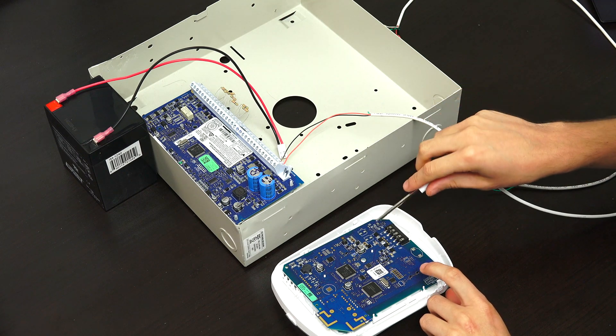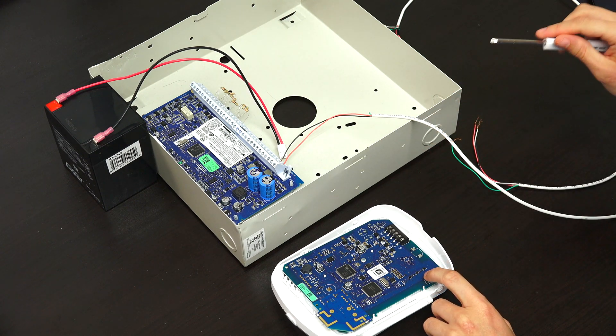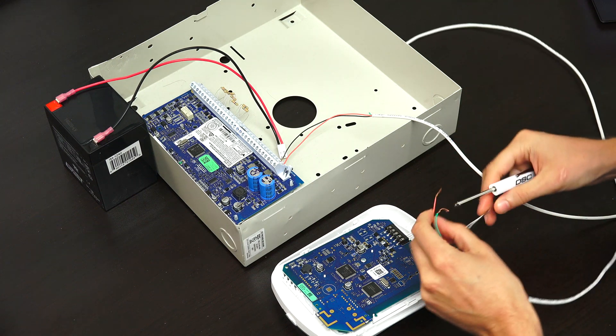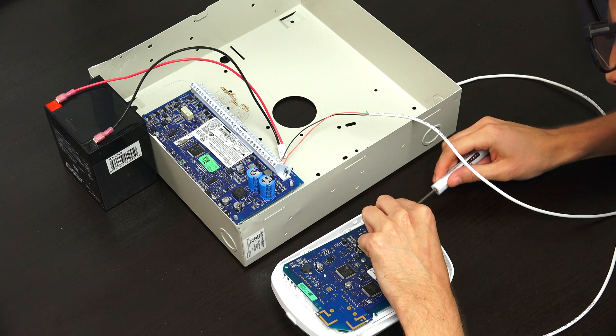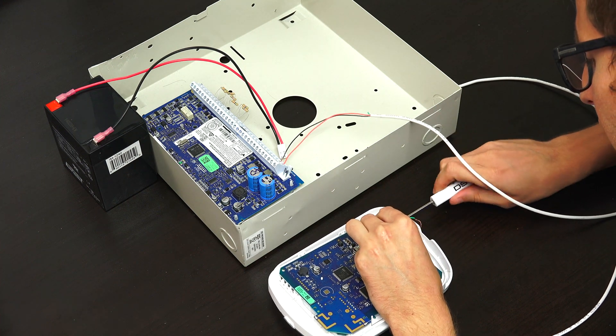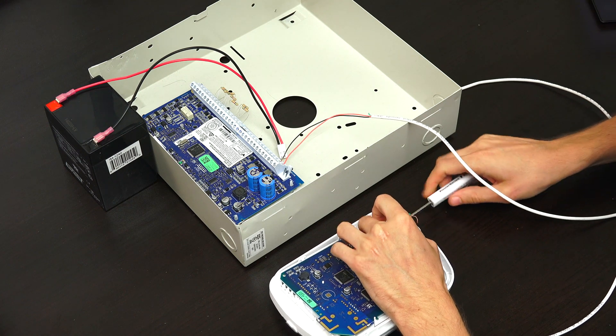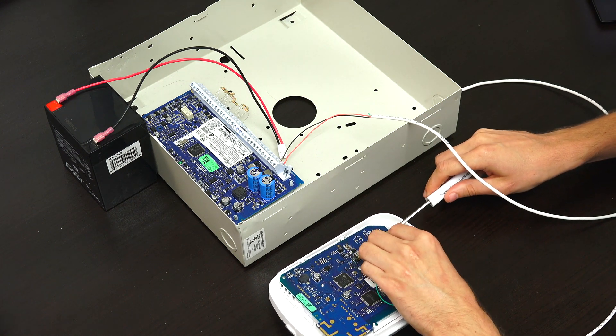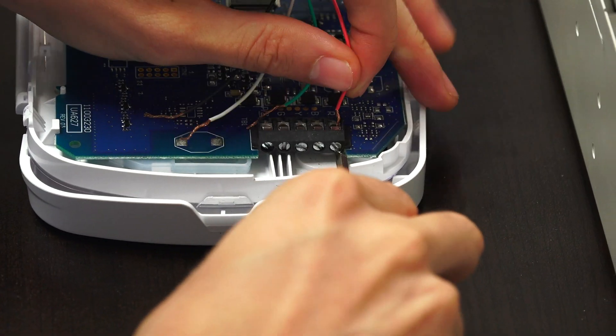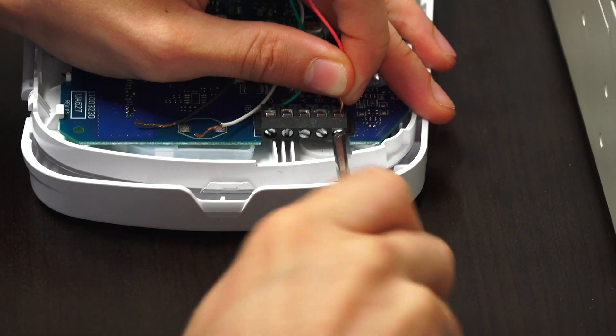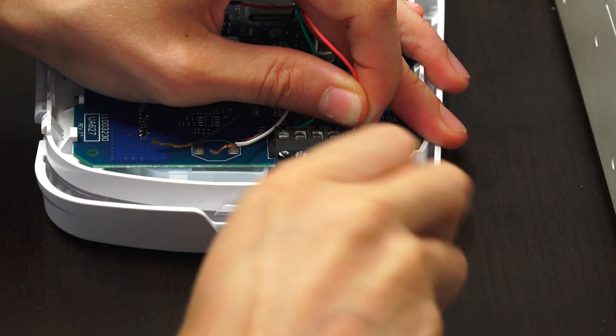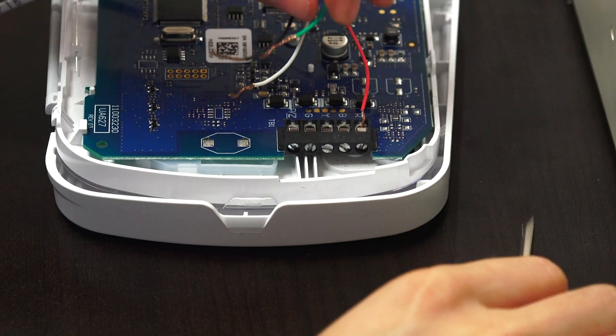You have R for red, B for black, Y for yellow (in our case white), and G for green. We're just going to go in and insert these. We have them loosened up already. Make sure they're nice and secure because we have had trouble with these coming loose. We're going to do the red wire into R and tighten this down.